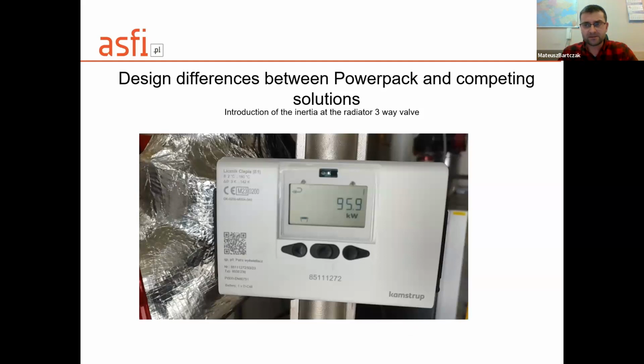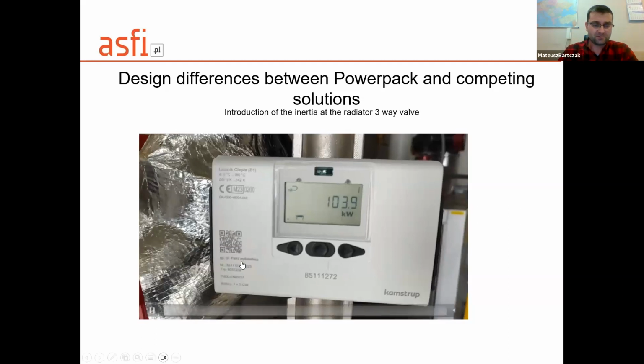Our clients have a heat recovery installation from one compressor. They asked us to make an installation from this one and a second one, the same power range, 160 each. And I asked my automation engineer to make me a record of the heat meters, but without the algorithm controlling the temperature of oil on the outlet of the heat exchanger. So we turn on a pump at constant flow, and we try to watch what will happen.